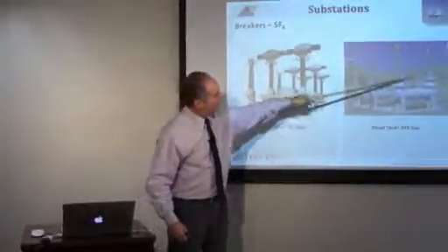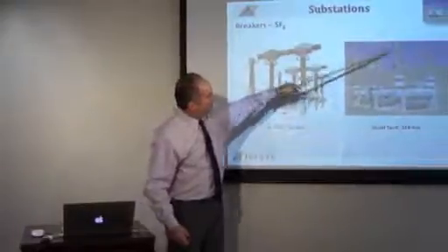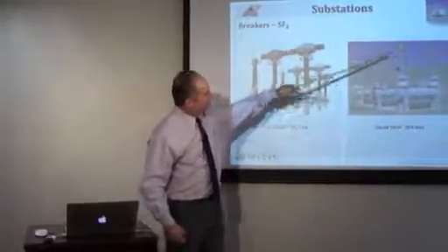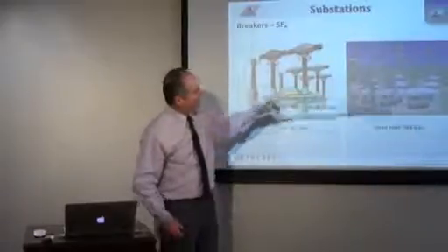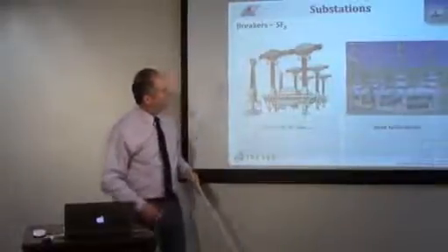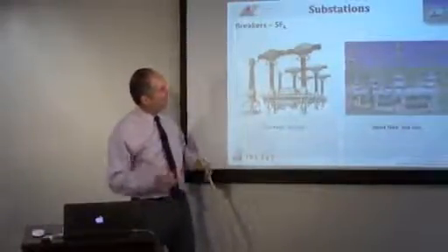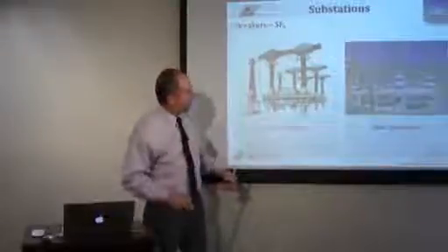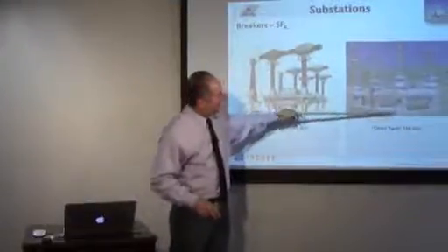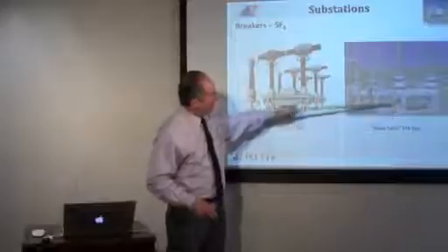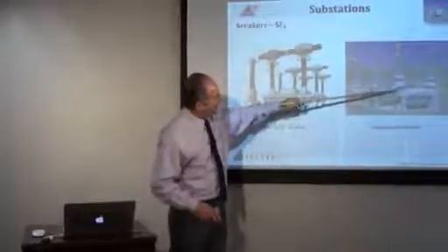These are voltage gradient rings. Up here, it allows the electric field to be equal all around, so it makes it a little bit more symmetrical and less stressful in certain areas. It balances out the electric field. These dead tanks are all grounded. There's ground wires there to the ground grid. It's all ground. You could actually touch all that.